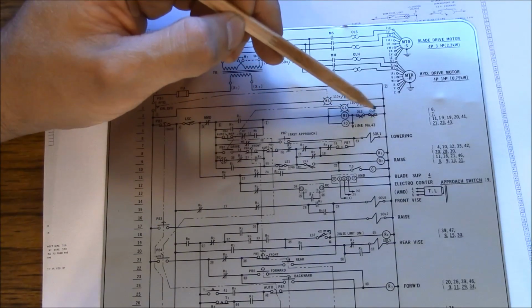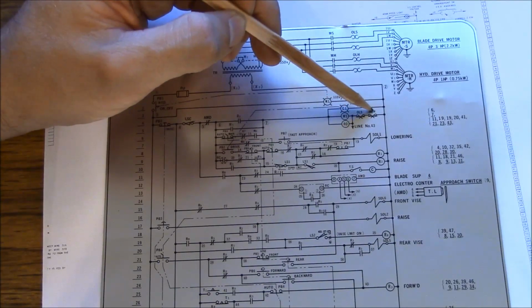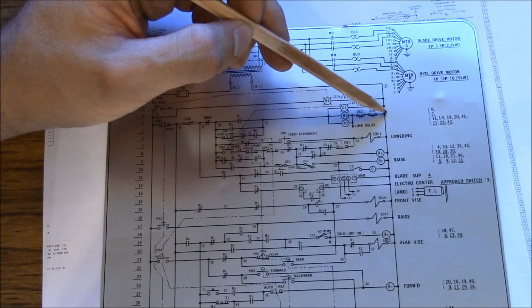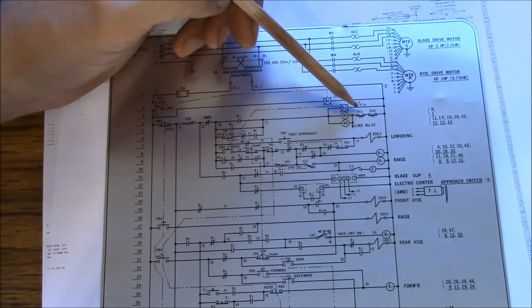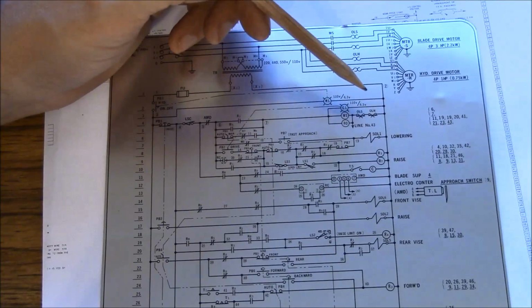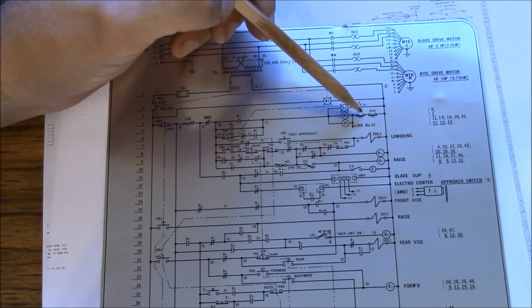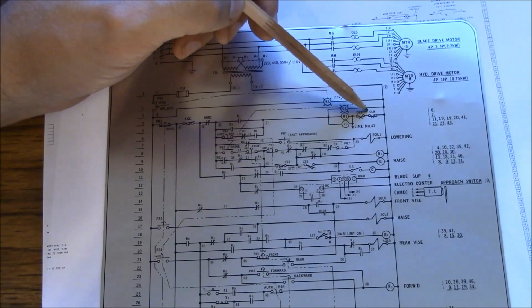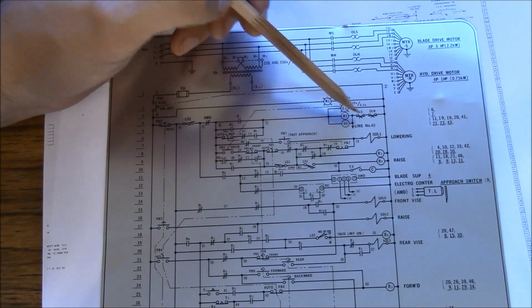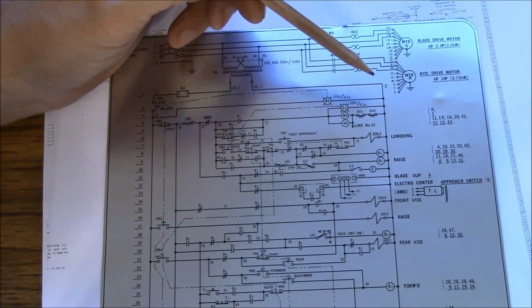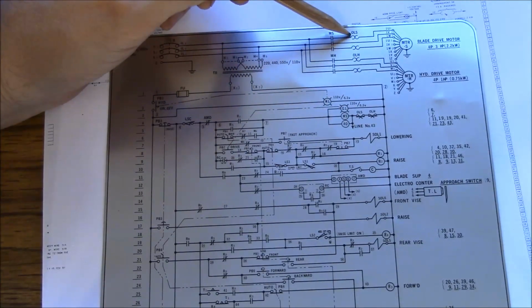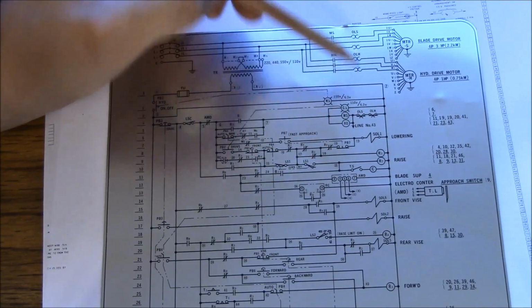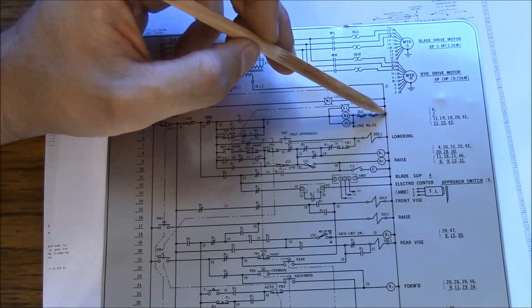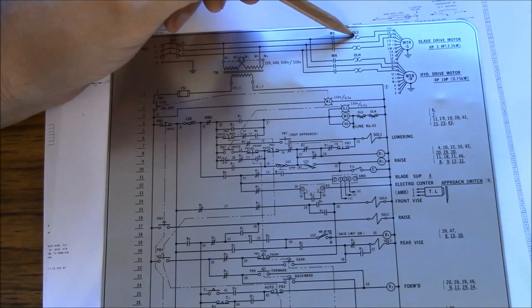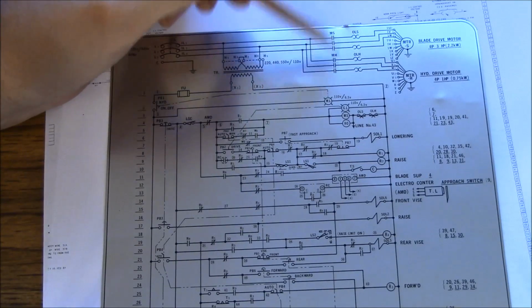So we can look at this side of the coil and see that there's really only one path for it to go from this side of the coil to the ground, and it has to go through this OLS and OLH, and these are represented by these X's, which means that these are normally closed, whatever OLS and OLH are. So anytime that those were open, that would kill the motor. And I think that we can remember that OLS is the heater. Yeah. So anytime that these heaters open up, it basically opens up the path to ground for the MS contact. So that basically means that anytime that the heaters trip out, the contact's going to open.